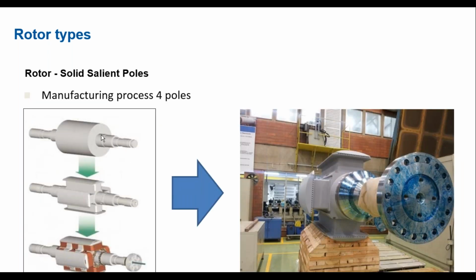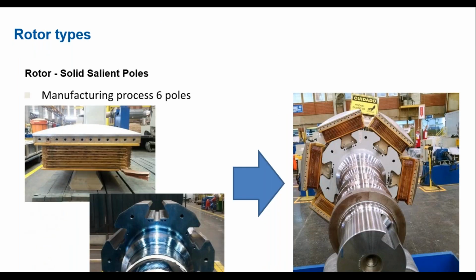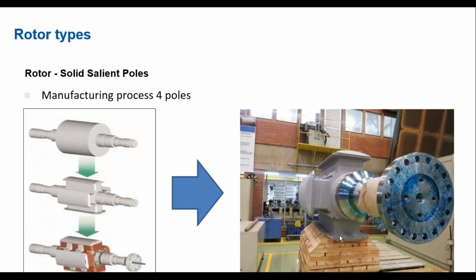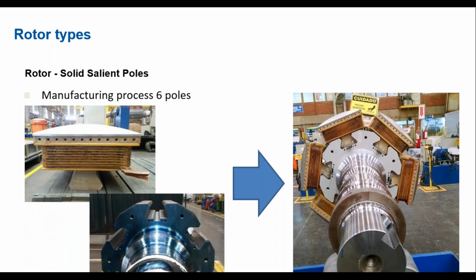This just gives some additional detail on the manufacturing process. So essentially a solid construction, machined, and then the field windings, either copper wire or copper bars, are inserted between the pole shoe and the shaft. This is the rotor design for a 4-pole machine. And the next picture is the same construction type, but for a 6-pole machine. These machines are unsuitable for low-speed applications. They find their place more in higher speed applications where high starting torques are required.